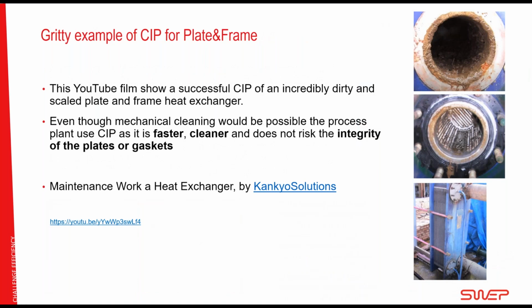This is not us. This is not SWEP at all. This is done on a different continent even, but I really like this YouTube film, and I would recommend it. It shows a plate and frame in an oil and gas application, and it's completely clogged up at the entry. It's a plate and frame of about man height, so it's maybe 5 feet tall, so it's absolutely possible to open it. What I found interesting in this down to earth, gritty application was that with a heat exchanger this dirty, they chose to do cleaning in place, and they reached this kind of cleanness by doing it.